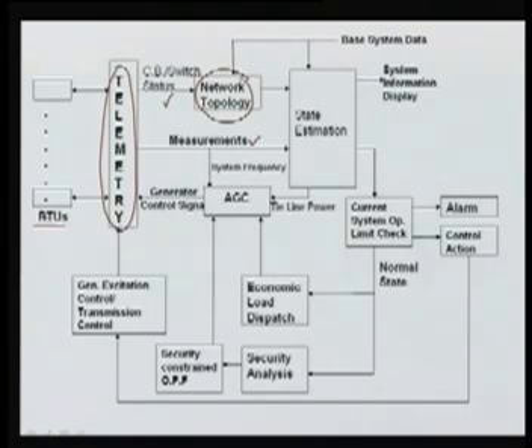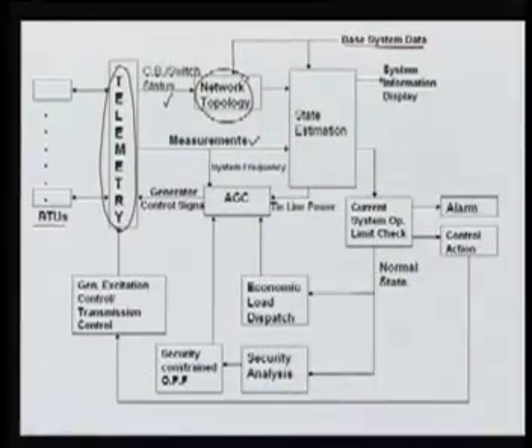This network topology requires the base system data, that is, the intact system information. At the same time, it requires the circuit breaker status of the various elements in the power system: the circuit breaker status of the transmission lines, transformers, as well as other circuit breakers. They come through the telemetry data, and then finally we can have the network topology, meaning the present network information, the network diagram. Based on that, this information is basically used in state estimation.